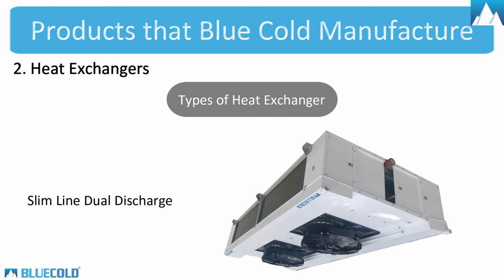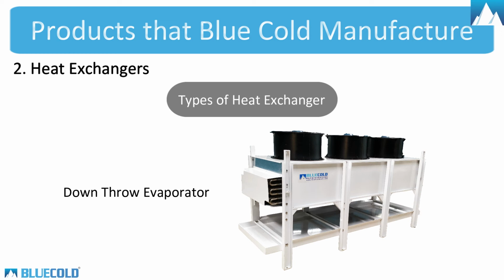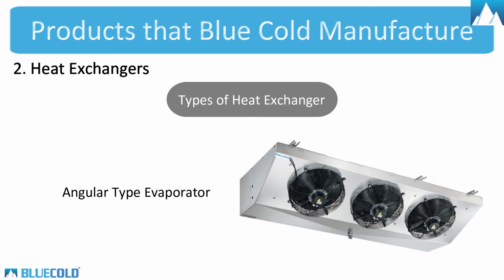Slimline dual discharge. It is a low air duct cooling unit that can throw air from both sides of its coil. It is suitable for ante rooms, cold room for dairy products and flowers. Down throw evaporator. It is suitable for chill cold storage, having an air throw pattern towards the downward of the unit. Angular type evaporator. It is designed in such a way that the flow of air should go directly to the product. Evaporator with chilled water and glycol. These evaporators are ideally suited for products requiring high humidity and low water loss during storage. These evaporators are designed to operate by cooling air with glycol or water to maintain high humidity and stable room temperatures for food preservation.